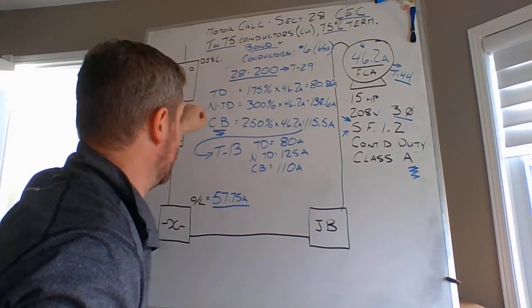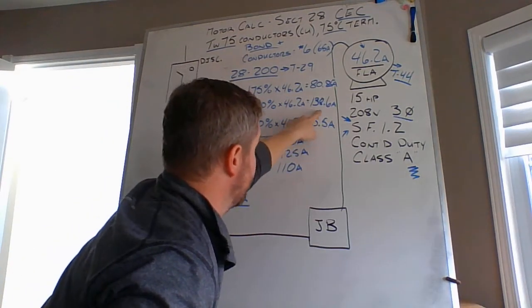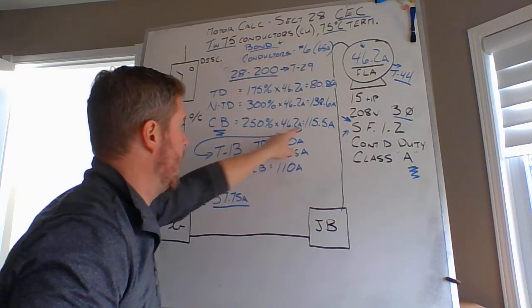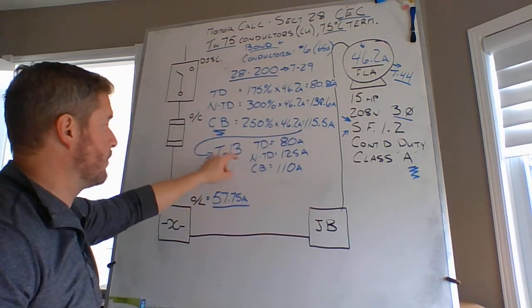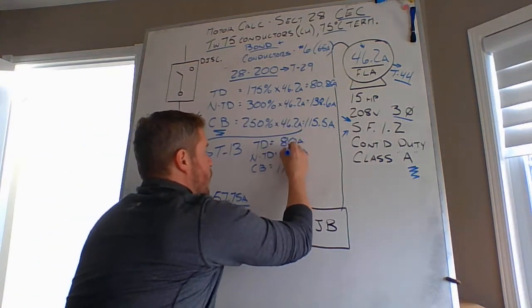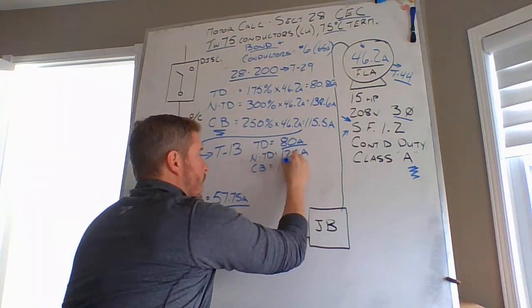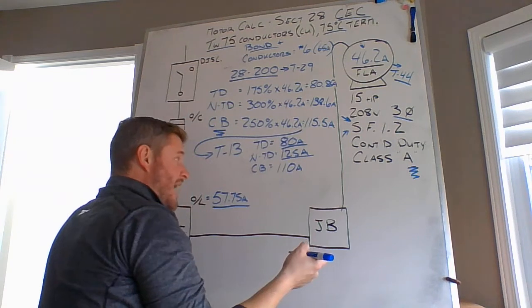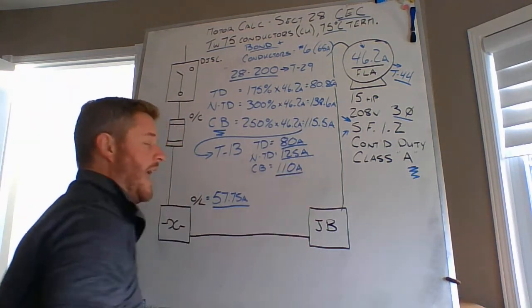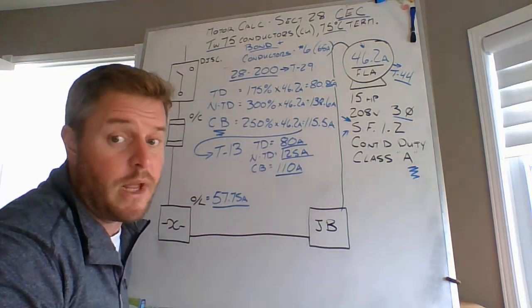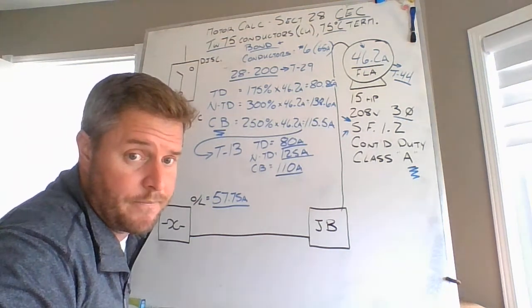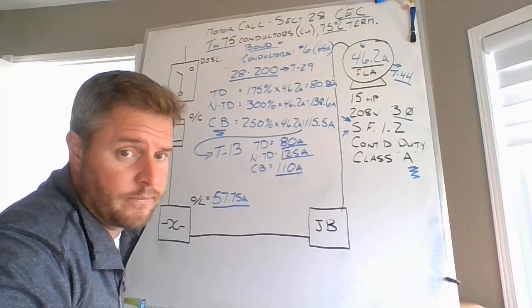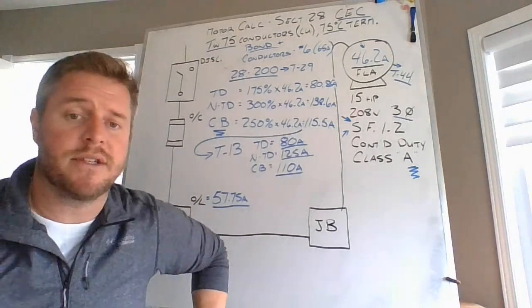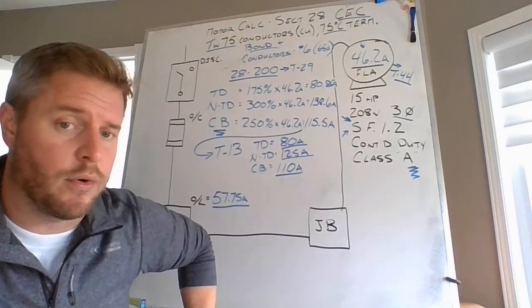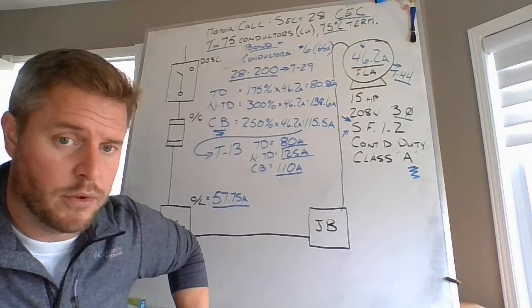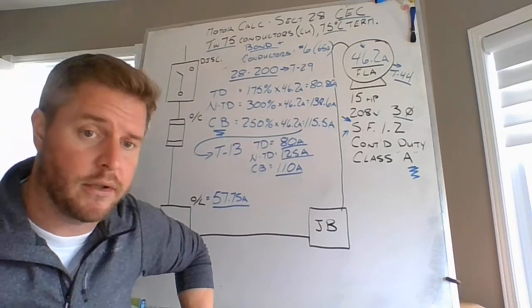80.85 for a time delay fuse. Okay, 138.6 for a non-time delay, 115.5 for a circuit breaker. My installed values would therefore be an 80 amp time delay, a 125 amp non-time delay, and a 110 amp circuit breaker. That would be my overcurrent protection. Now would be a good time to hit pause and make sure that you have the same values recorded as myself. Okay, when we're looking at our installed values versus our calculated values.